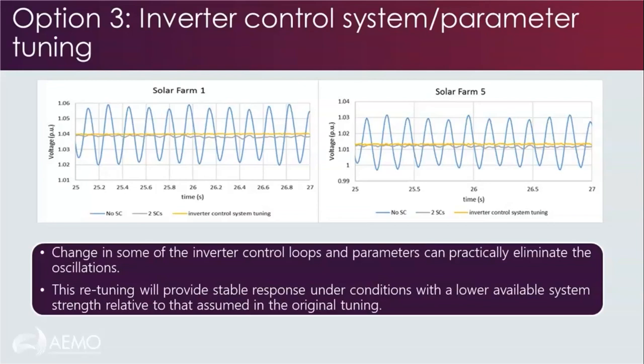In this case, obviously, tuning would not increase the background system strength available to the inverter-based resource, but what it does is make sure that we can still achieve a stable outcome as far as the inverter-based resource is concerned, with recognition that the system strength is lower than when the original design and tuning of the inverter-based resource was conducted. So some changes would need to happen to ensure that stability is still achieved, both in the small signal and large signal sense.